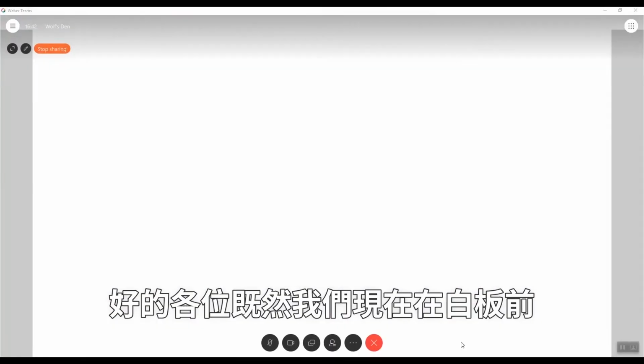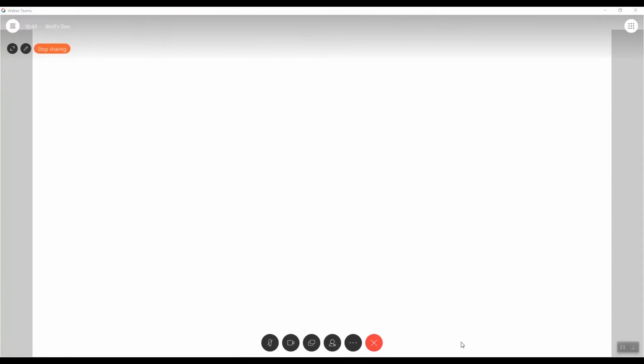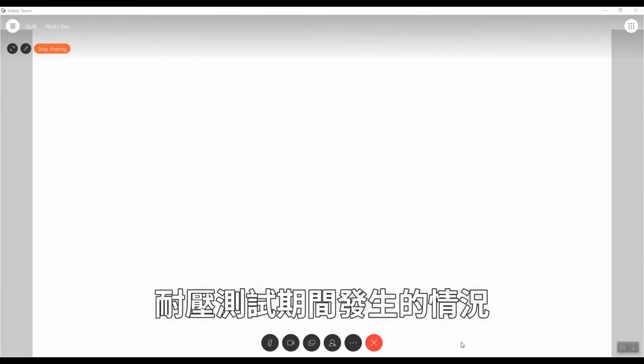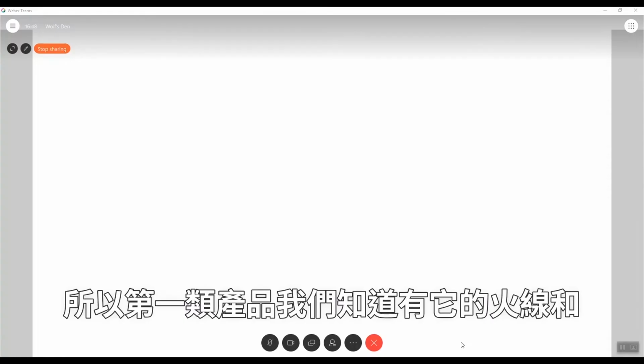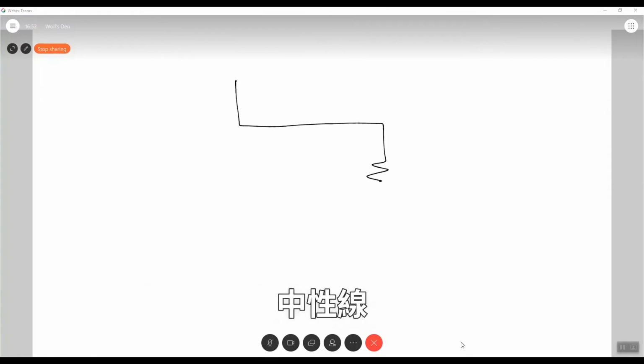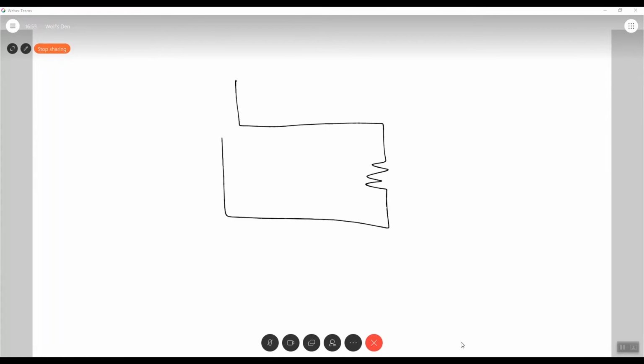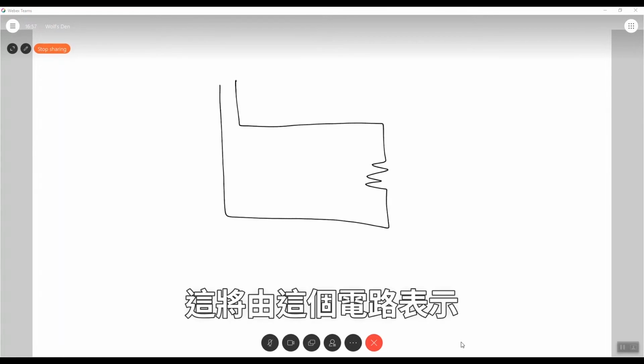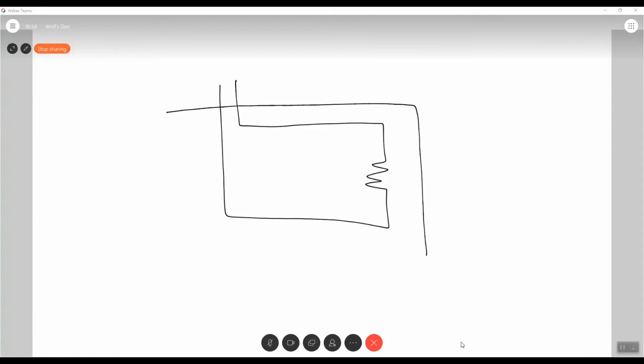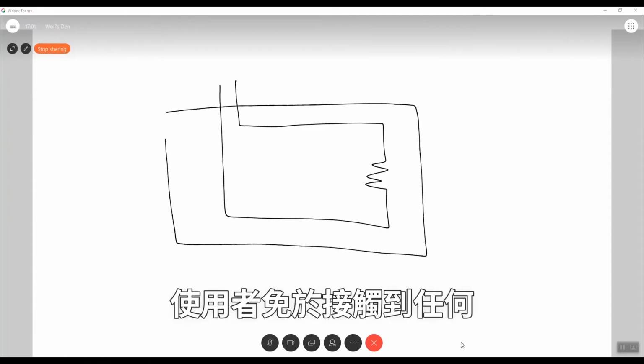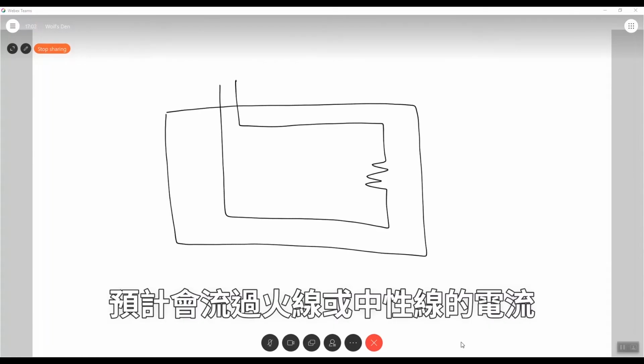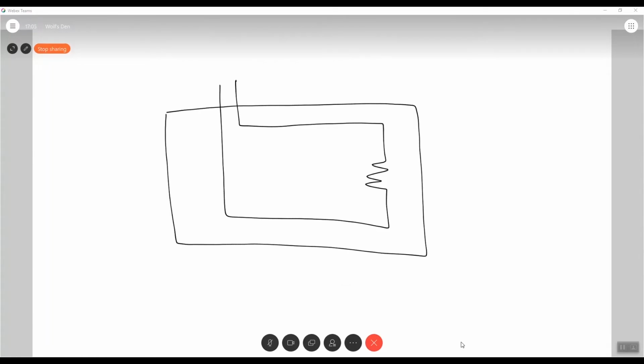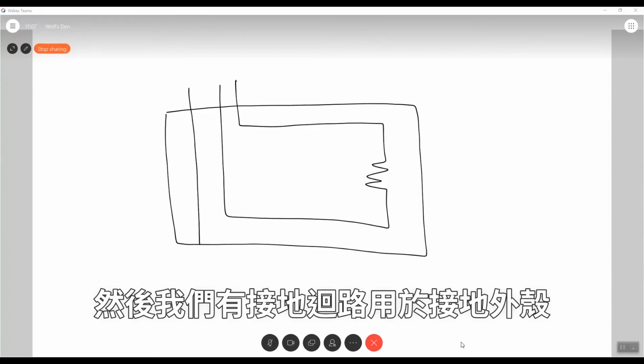Okay guys, so now that we're here in front of our whiteboard, I can draw some diagrams to better explain what's happening during the Hipot test. So, a Class 1 product we know has its line and neutral, which will be represented by this circuit. We have a chassis that's there to protect its users from coming into contact with any current that's intended to flow on the line and neutral. And then we have our ground circuit, which is used to ground the enclosure.